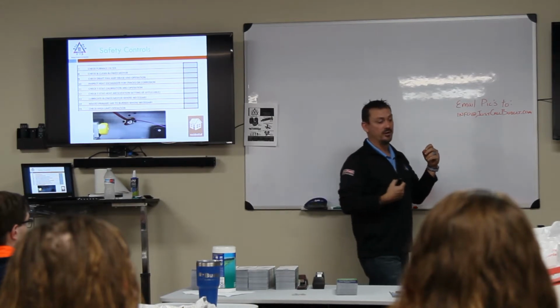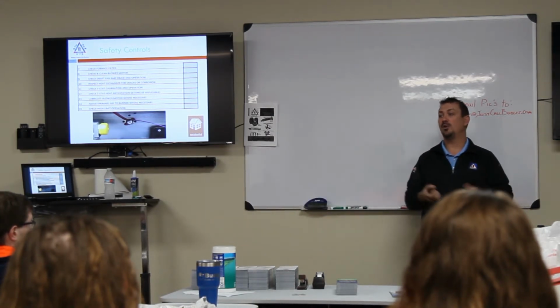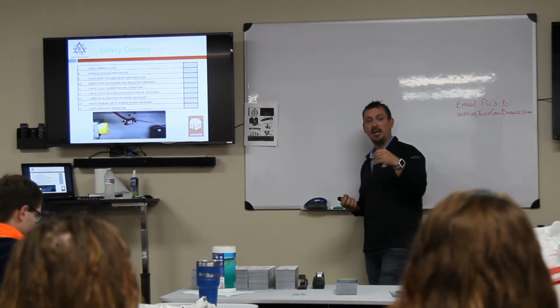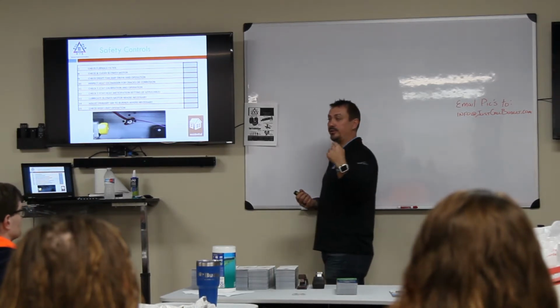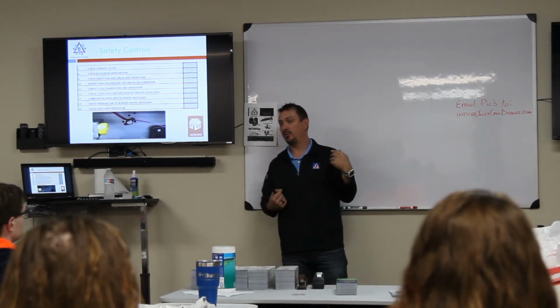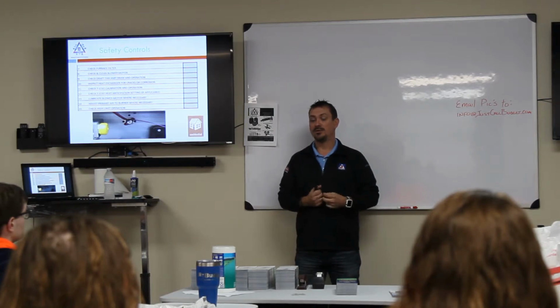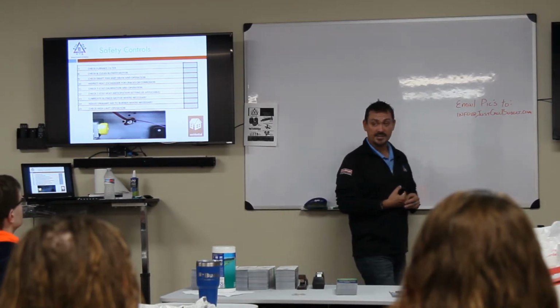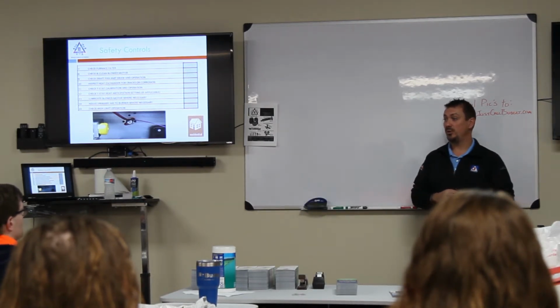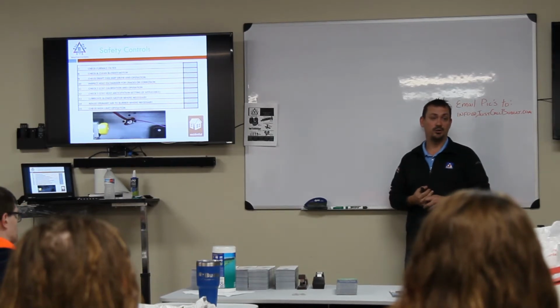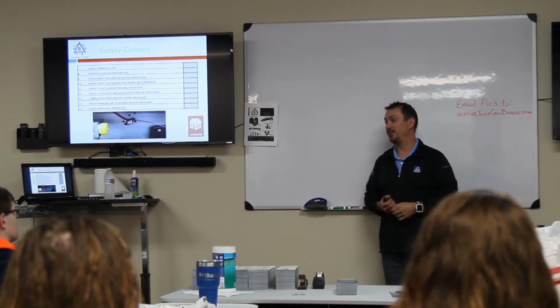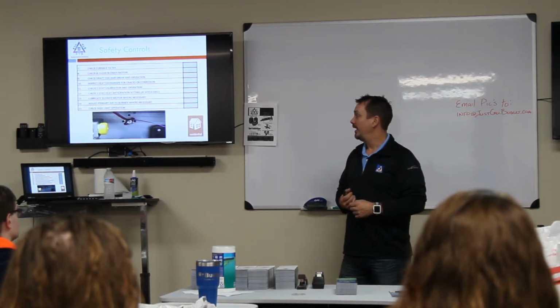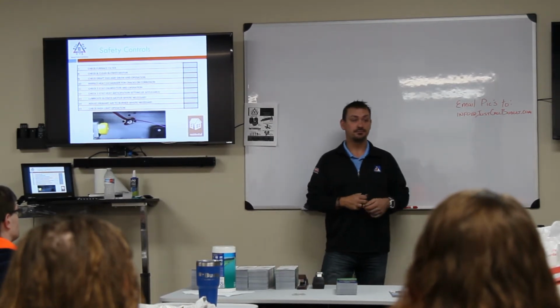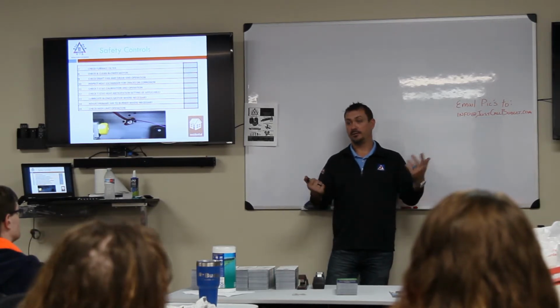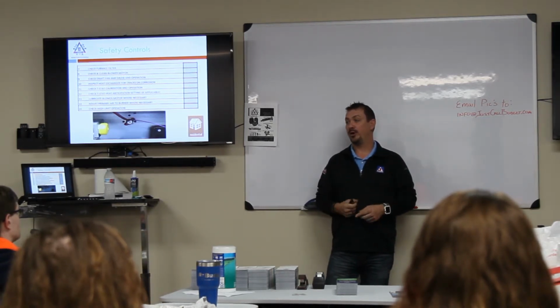But it's large enough that as soon as it shuts off, it allows the pressure to equalize, and debris and moisture will get inside that little tiny weep hole and not allow that pressure switch to function properly. So yes, 92% of the pressure switches that you replace are actually good. So should you wait 2.5 days and then come back with that same pressure switch? No, they're $14. Go ahead and replace that thing. They're cheap.